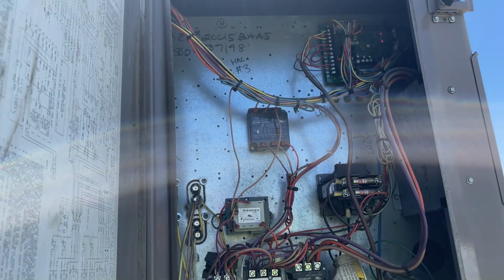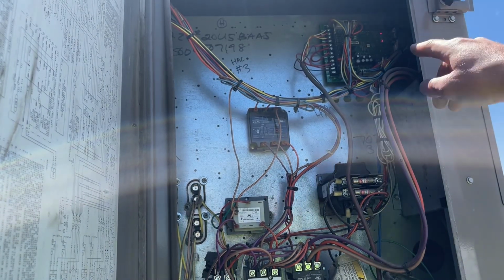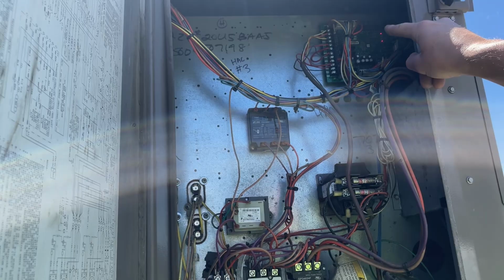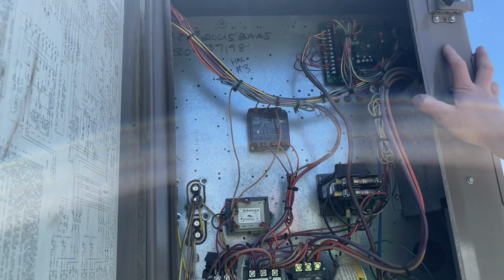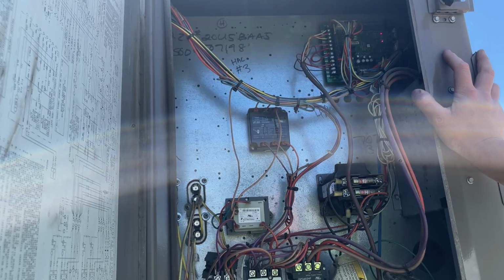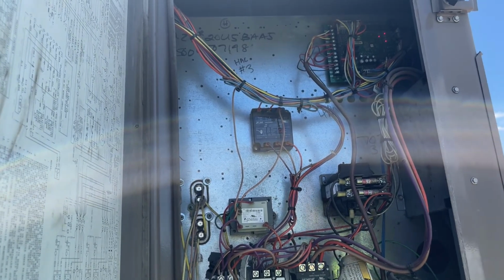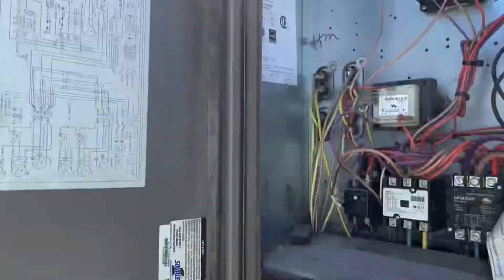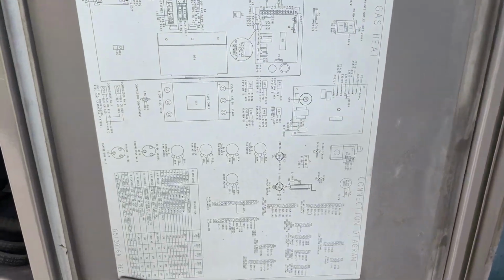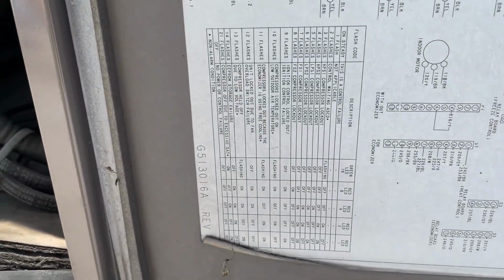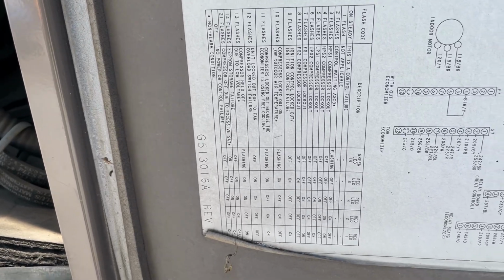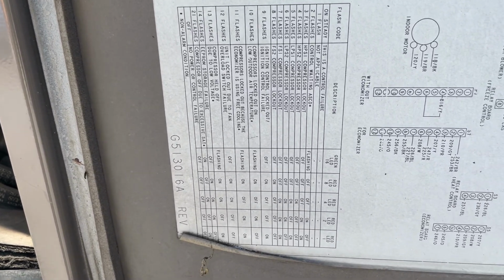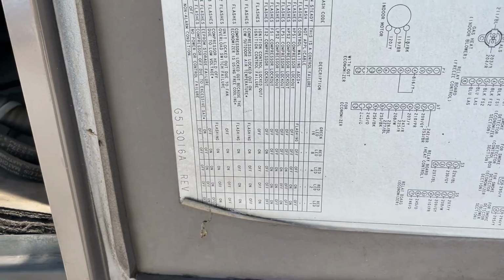Okay. All right. As you can see up here, we have an error code on our board, that flashing red light. Let's count the beeps or the flashes. 1, 2, 3, 4, 5, 6, 7, 8, 9. 9 flashes. What does that mean? Come over to our handy dandy schematic here, or our error code chart, and as you can see, 9 flashes. Ignition control locked out. Ignition control failure.